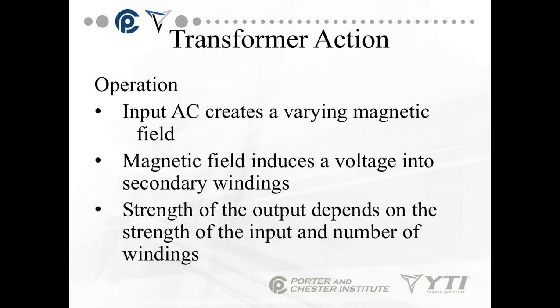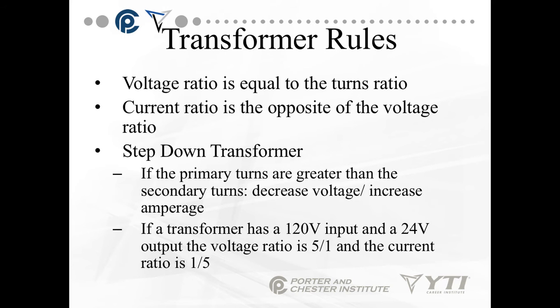Okay, the way this actually works is the input AC, or the primary alternating current, creates a magnetic field. That magnetic field induces voltage onto the secondary windings. What I mean is, anytime you put a coil of wire into a magnetic field, you're going to start getting current out of the coil of wire. The strength of the output depends on the strength of the input and the number of windings of both the primary and the secondary side. That's called a voltage ratio. The voltage ratio is equal to the turns ratio. The current ratio is opposite of the voltage ratio.